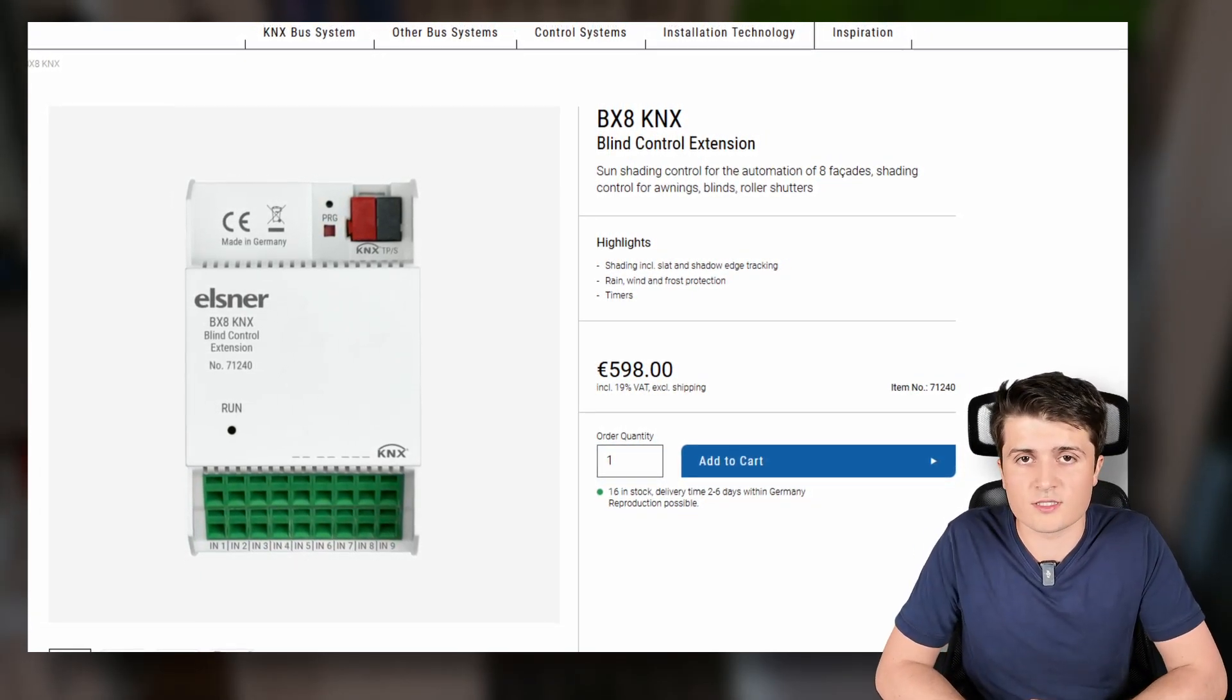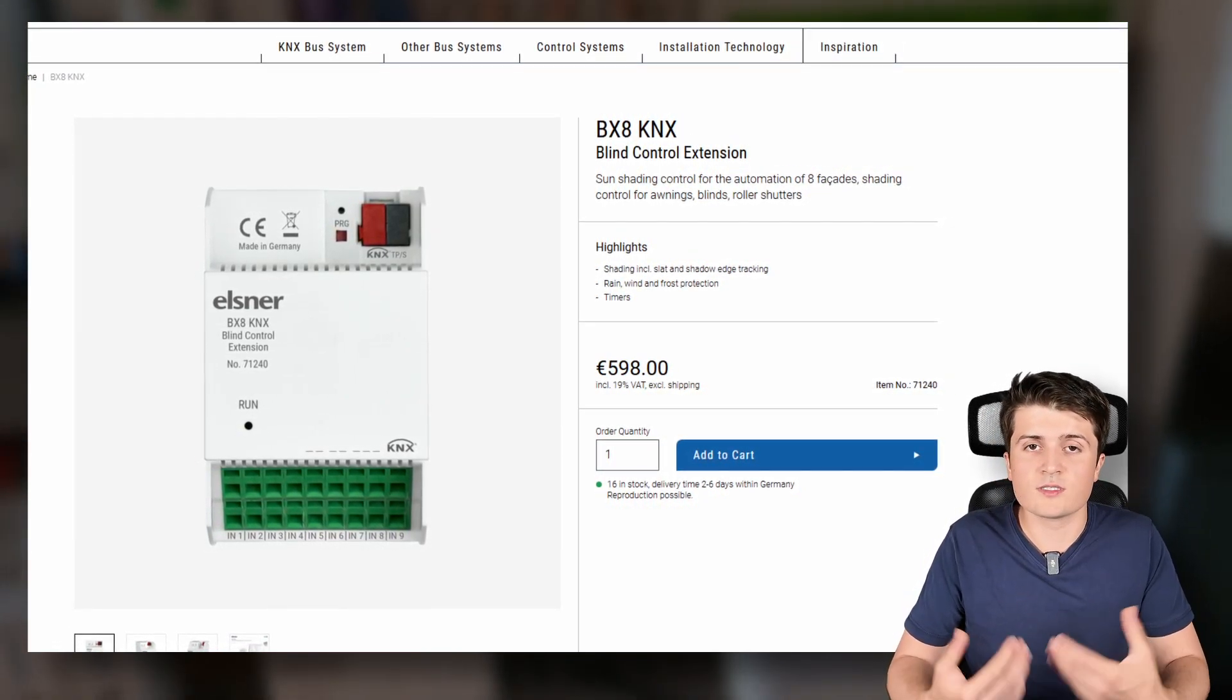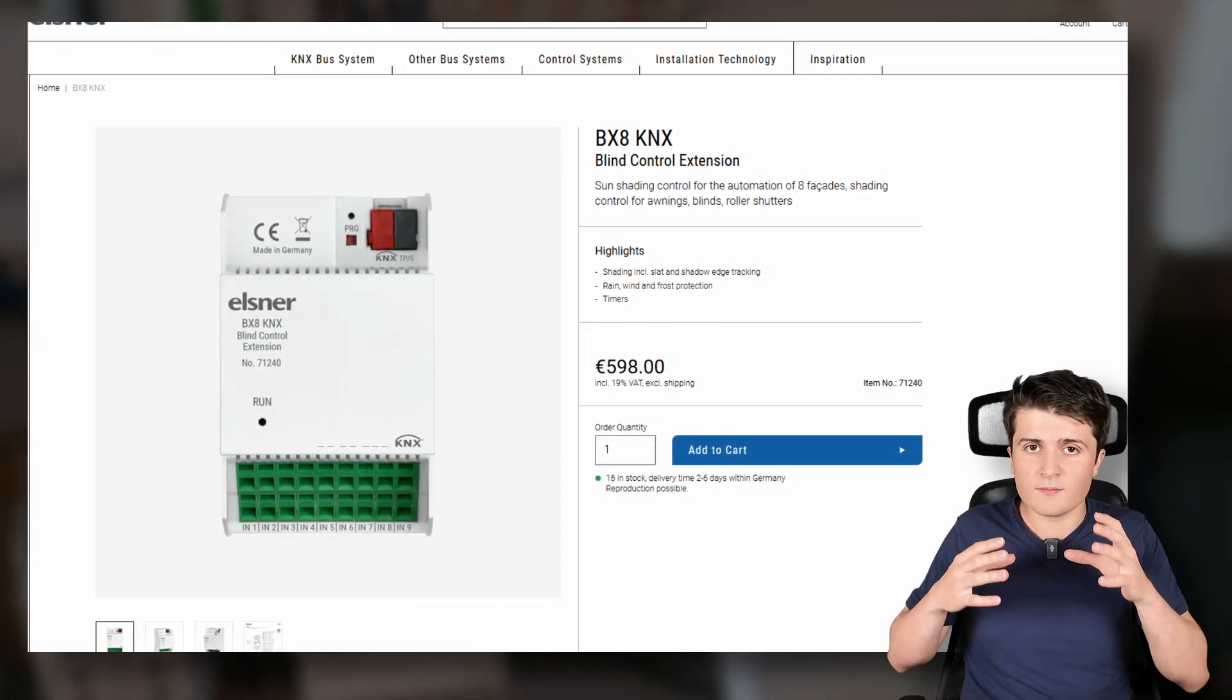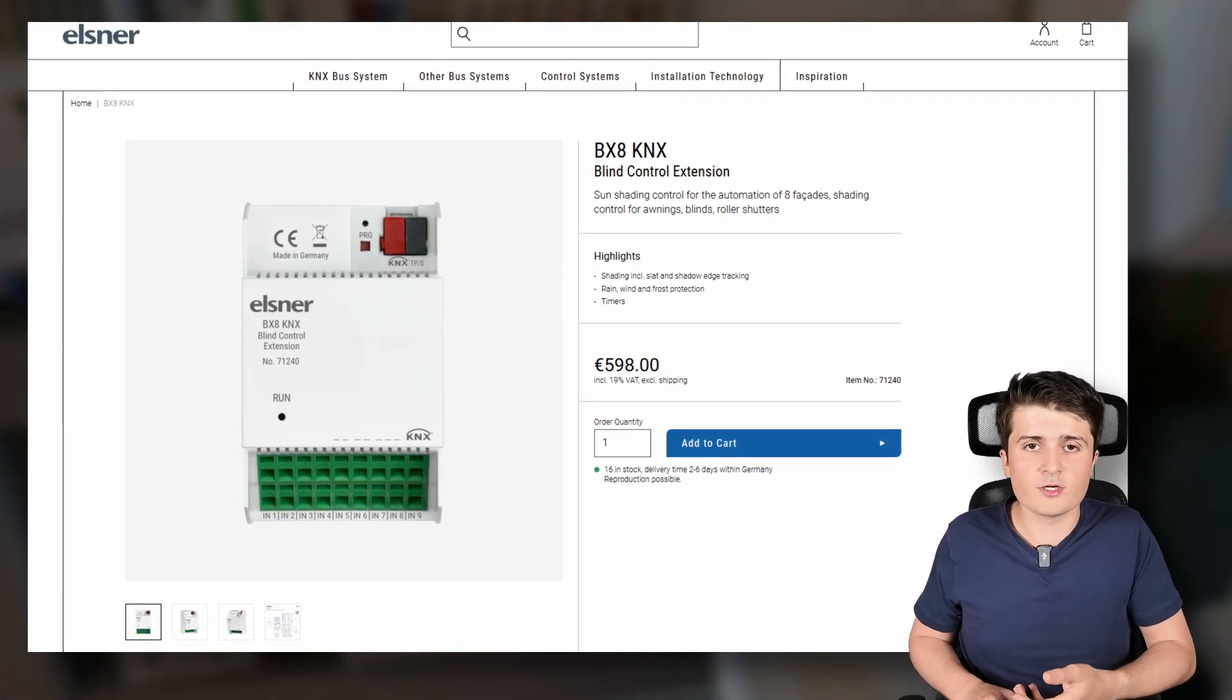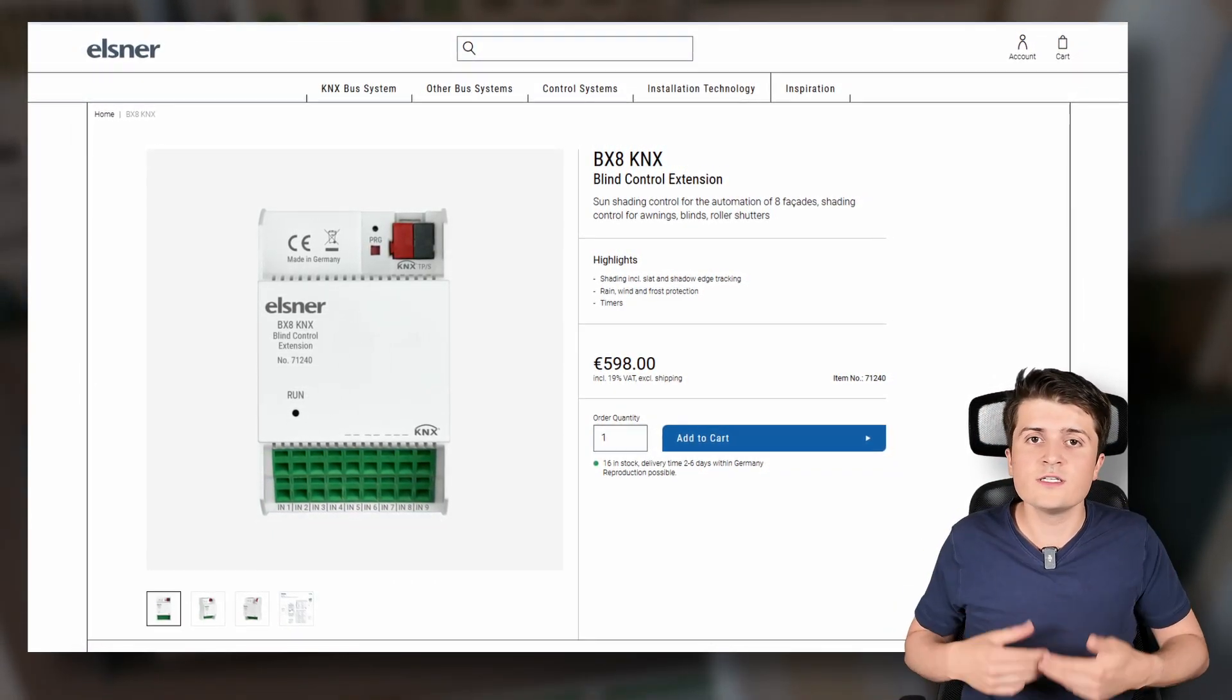And then you can use for example the Elsner BX8 KNX device because this device is not a sunshade actuator but instead a device that implements these automations into the device so that you can then connect it via group addresses to your sunshade actuator. So by that you basically retrofit your existing sunshade actuator with those automations this device this Elsner device then offers. So as I mentioned definitely not a device for every KNX installation but may be interesting for you if you have to retrofit a KNX installation with those automations.